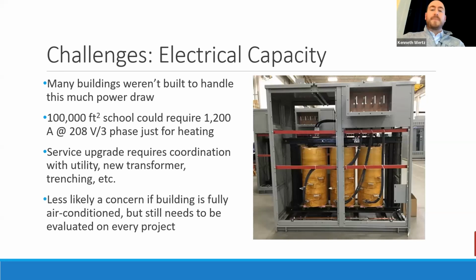So the first one, probably not a surprise, is that a lot of these older buildings that we're talking about that were built, you know, 30, 50, 70 years ago, they just weren't designed to have this much electricity coming into the building. They may or may not have had some upgrades over the years to add air conditioning, but even buildings that have some air conditioning are likely going to exceed what the capacity is of the electrical systems if you try to fully convert everything to heat pumps for the heating system.